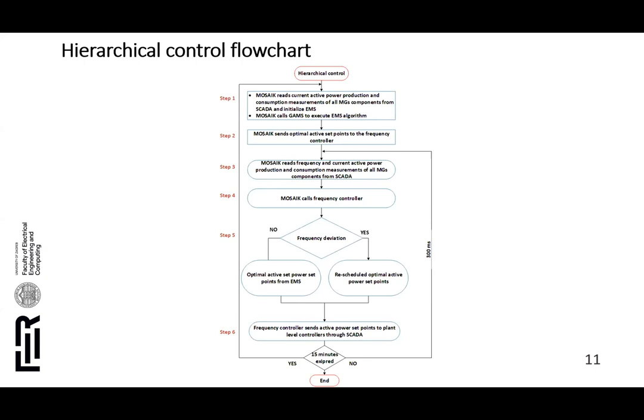In step three, MOSAIK reads frequency and current active power measurements of all microgrid components from SCADA and forwards those measurements to the frequency controller. In step four, MOSAIK calls the frequency controller to execute. If frequency measurement doesn't deviate from nominal, the frequency controller sends the optimal set points through SCADA to local plant-level controllers. In the case of frequency deviations, the frequency controller sends rescheduled optimal active power set points to provide primary reserve. Steps three to six are cyclically executed every 300 milliseconds.